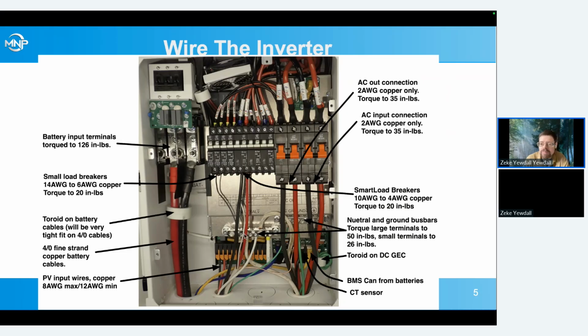And if you're doing full power, if you're doing off grid, this can be different, but connected to the grid, this is a full 100 amp pass through. So you want 2 gauge copper. Don't want to have undersized cables here. And also to note, we've got a toroid on our DC grounding electrode conductor. That's our DC wire going back either to our ground rod or our UFER or back to the AC service.